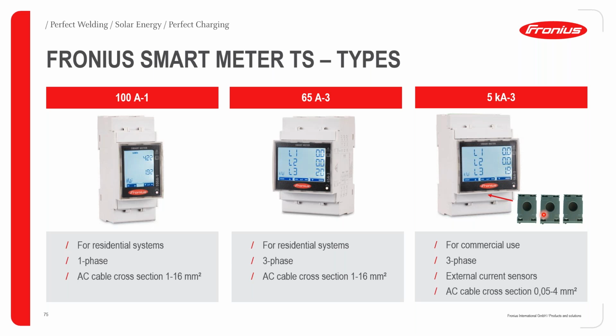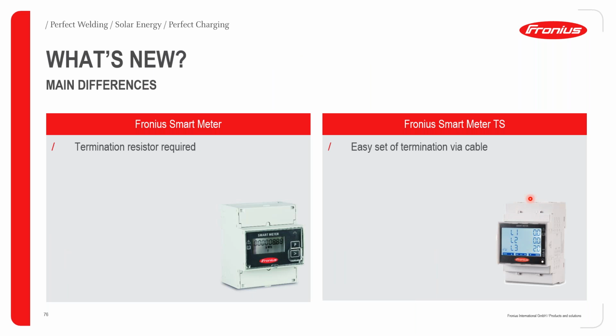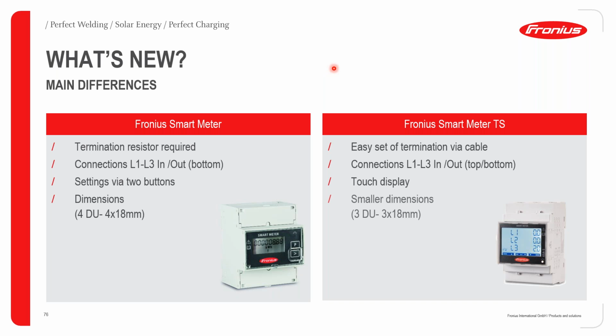In terms of the differences between the 2 smart meters, the old and the new series, we can try to highlight them here for you. In terms of the connection, when you're doing the setup of the smart meter, for the older version you need an actual physical termination resistor, whereas for the new smart meter, all you need is a termination cable. You're going to be doing a bridging connection between designated terminals, and that achieves the 120 ohms required for termination.